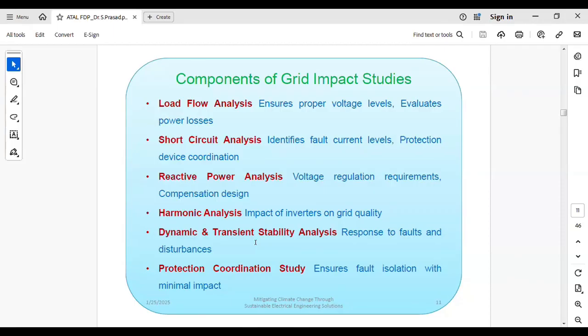So what are the different types of faults you need to apply at the PV end, and you have to check that the generators in the existing plant should not get disturbed, or in what kind of fault the generators are getting unstable. So that is also coming under the transient stability analysis.